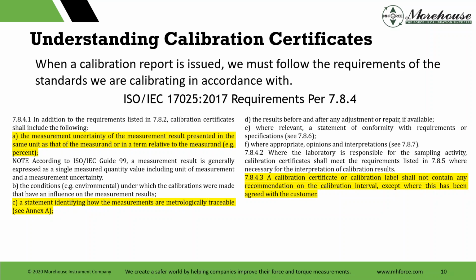For Section 8.4.1, the measurement uncertainty of the measurement result presented in the same unit as the measurand or in a term relative to the measurand, e.g. percent. A statement identifying how the measurements are metrologically traceable. That's really important here. We're going to discuss it. And then 7.8.4.3, a calibration certificate or calibration label shall not contain any recommendation on the calibration interval except where this has been agreed with the customer.